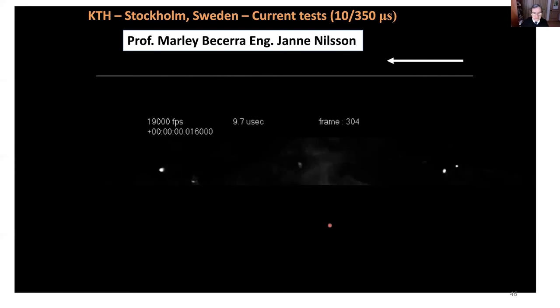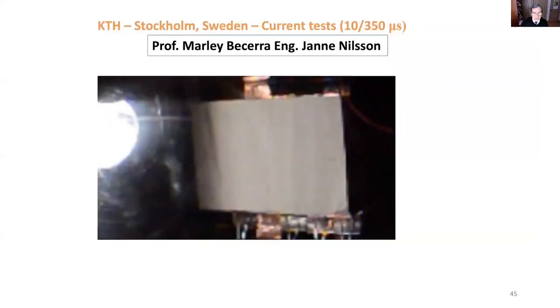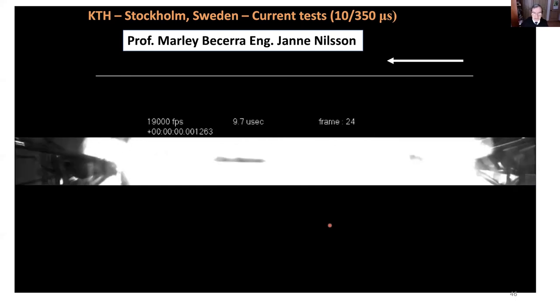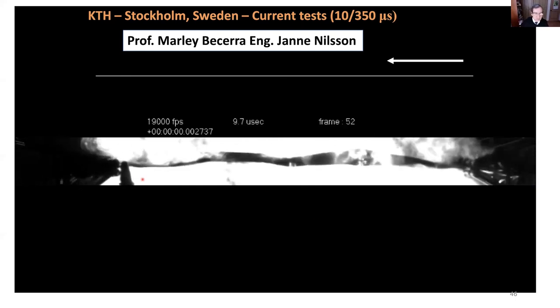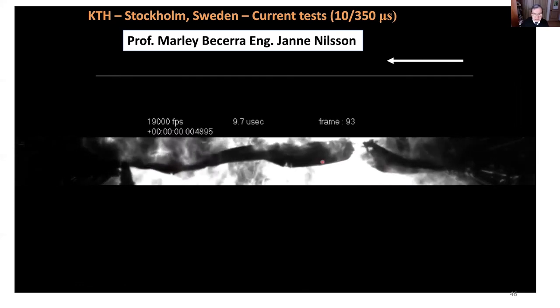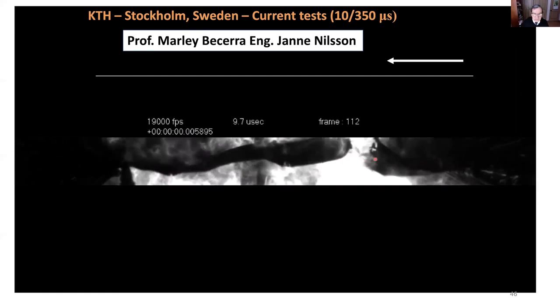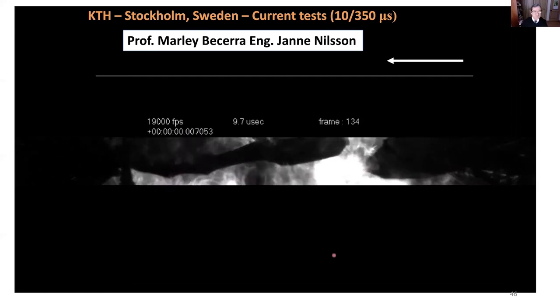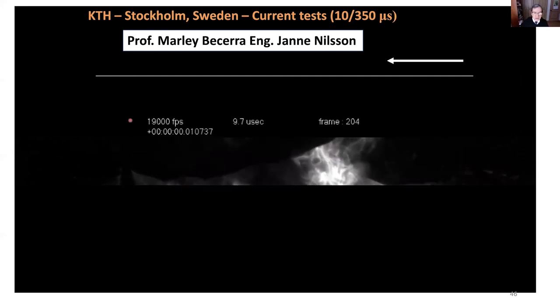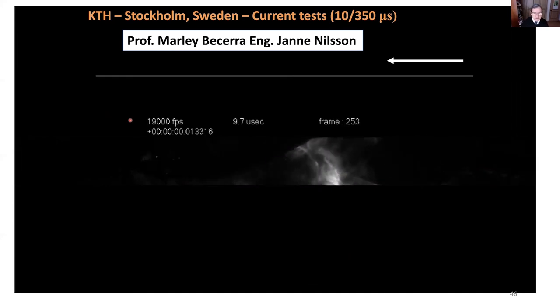Finally, using a fast-speed camera with Professor Marley Becerra and Engineer Janne Nilsson, current was applied and we observed several places where the material was vaporized and destroyed, but plasma connections still carried the current. Small sparks were visible on the rest of the material until it was completely vaporized. The camera operated at 19,000 frames per second, and the experiments used 10/350 currents.